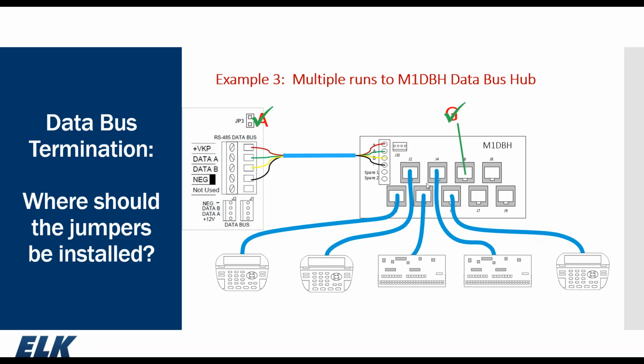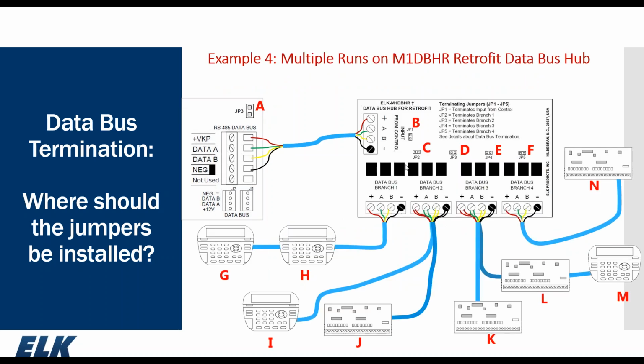And so forth. And remember, we can daisy chain these hubs together, so don't think you're limited to only 9 devices. You can have multiple hubs daisy chained together. In the case of the retrofit hub, if we consider each branch as its own independent 485, just like the M1 main control, in this example, we have just the one hub. So we terminate the main control, JP3. We terminate the hub itself. This is JP1. Branch 1 is a daisy chain of 2 keypads. We terminate the last keypad and the branch. JP2 is assigned to branch 1.